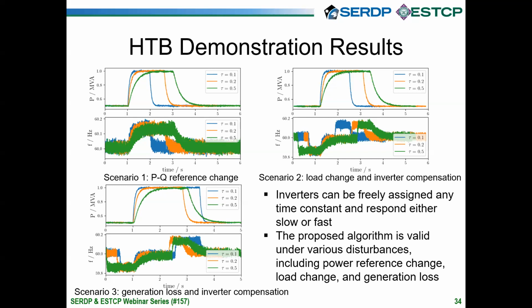So if you want it fast, don't be faster than 0.1. Another thing the designer may want to coordinate is with the primary and secondary frequency response of the grid, especially if you have synchronous generators in the system. For example, primary frequency control takes a few seconds, and secondary frequency happens at the tens of seconds or minute level. That's the basic guideline.